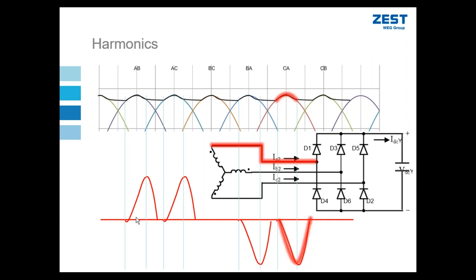So the end result of that is this very funny-looking waveform. Instead of drawing a nice sinusoidal waveform like a motor directly connected to the line would do, I draw these funny bunny ear type waveform shapes from the supply. And that is a distorted waveform, and that will lead us into our discussion on harmonics.